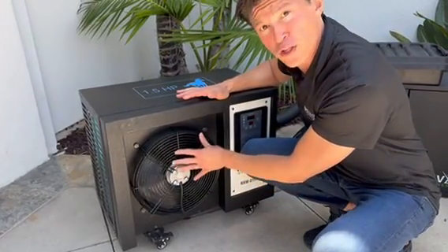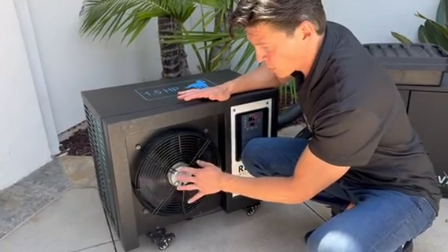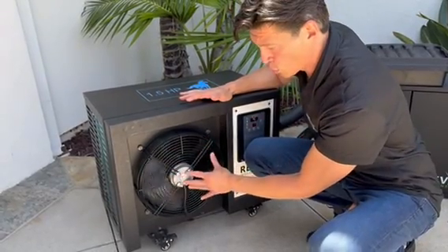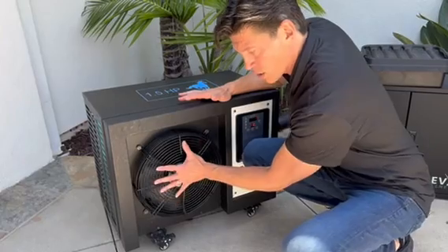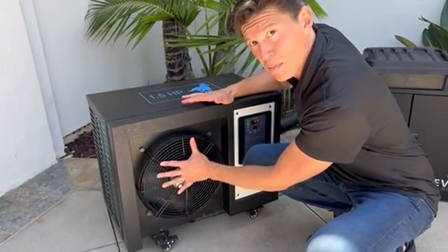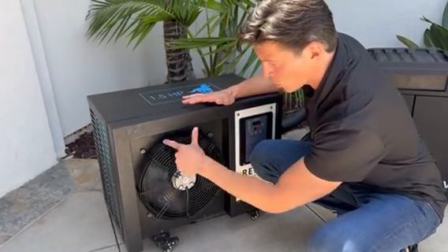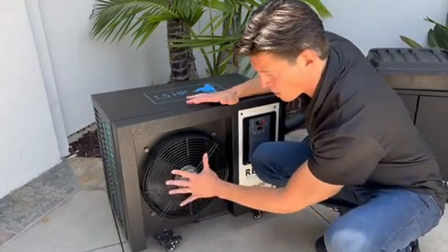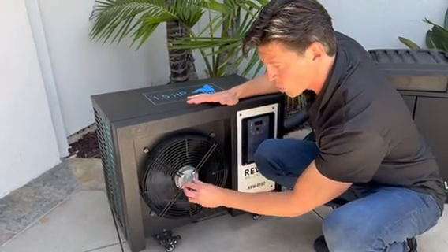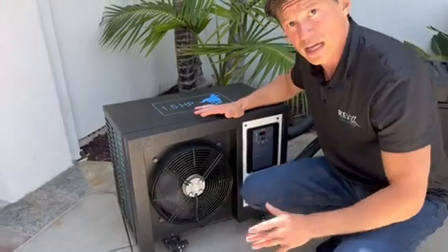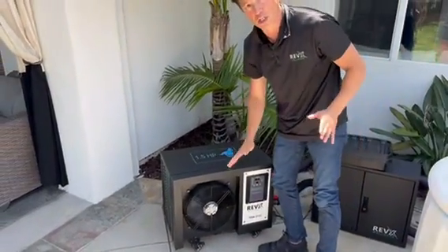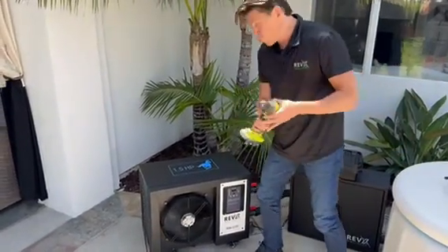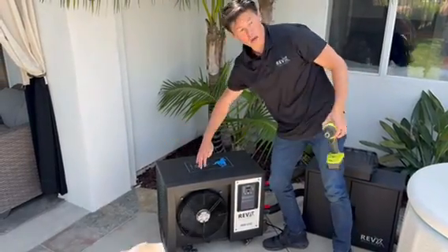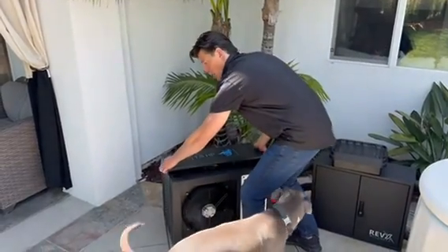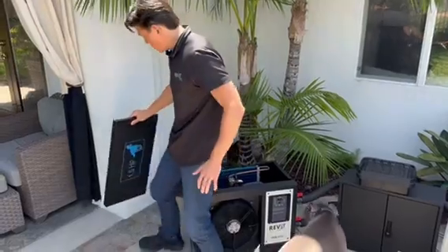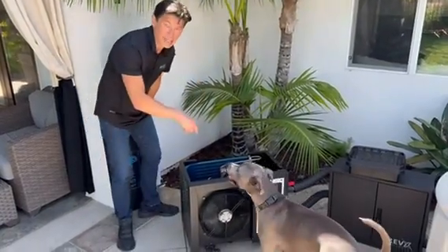So the fan has a front grill, and sometimes this front grill can make noise. To troubleshoot that, simply start putting some pressure on here to see if that will stop the noise. If it does, you may need to adjust these screws around on the grill or even here, okay, to bring the noise level down. If the noise comes from the inside of the chiller, take a drill and remove 6 screws around the lid and then lift the lid straight up. Once you lift the lid straight up, look inside the chiller.